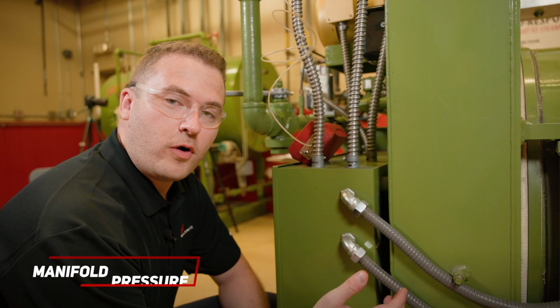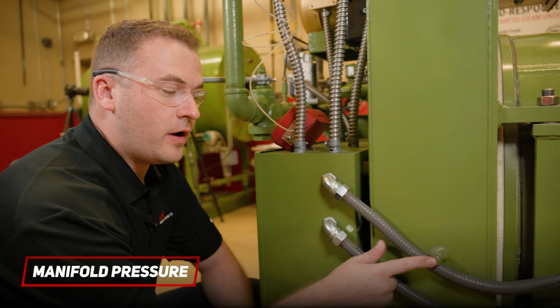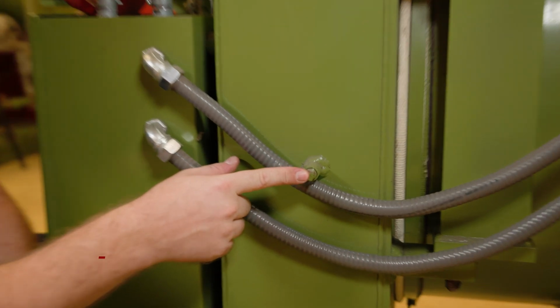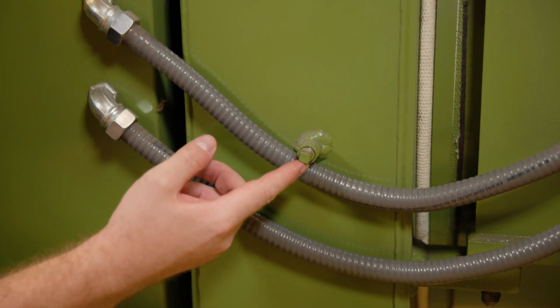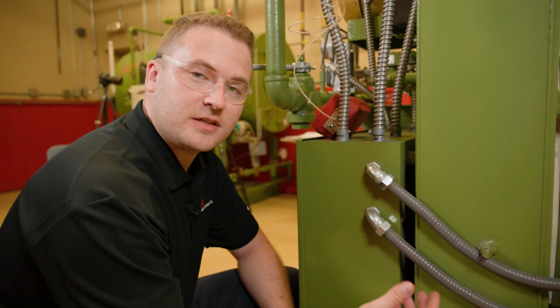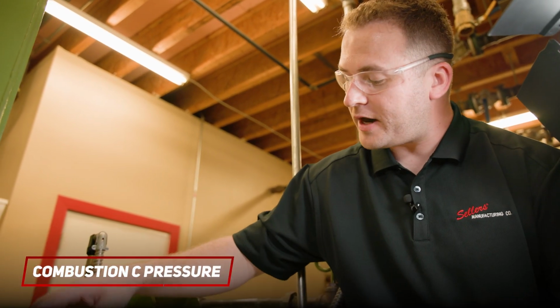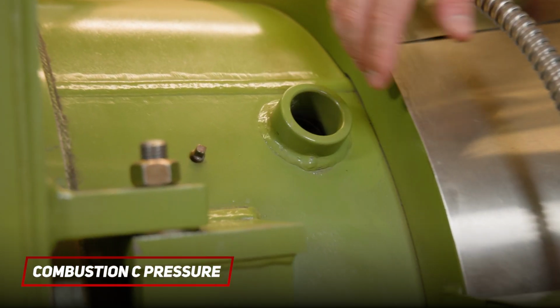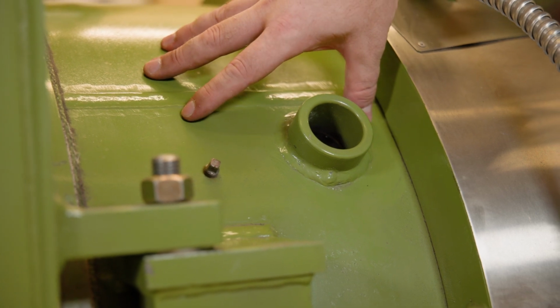Here on the side of the boiler, on the front door, on the lower end, we have a manifold test port. This is going to measure the manifold pressure of the air and fuel that is mixed before it reaches the burner. And the last pressure we're going to get is our combustion chamber pressure on the side of the shell of the boiler that measures the pressure inside the combustion chamber.